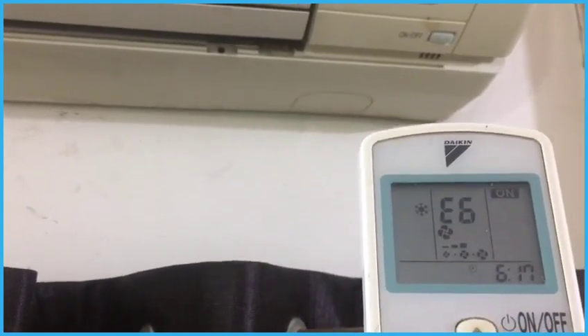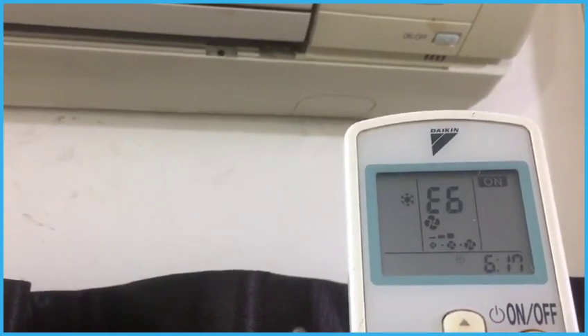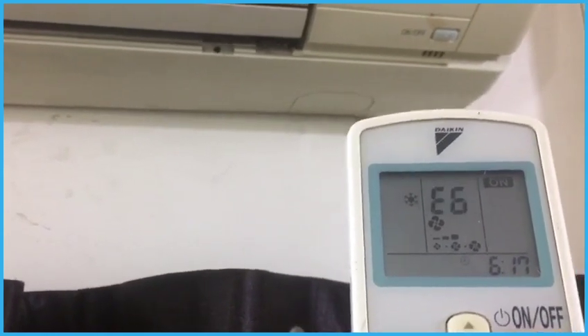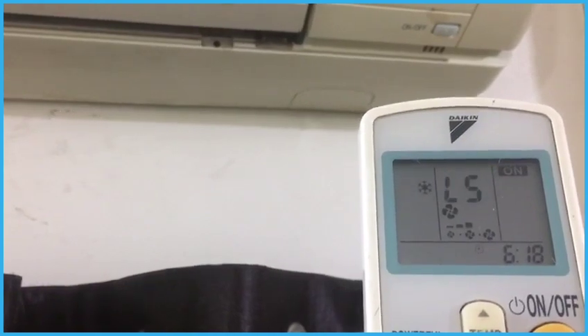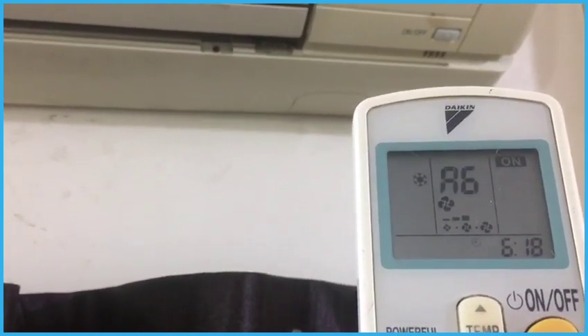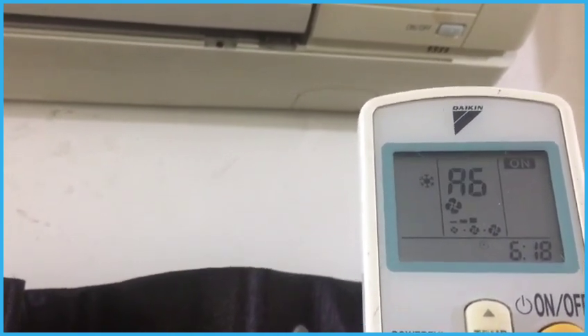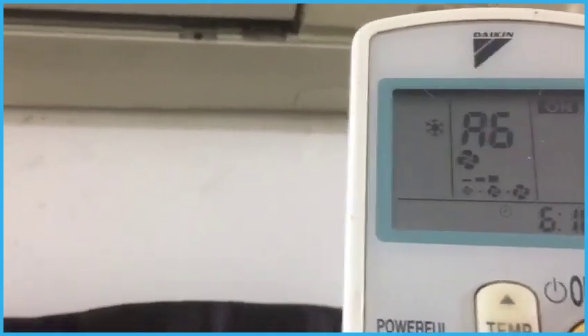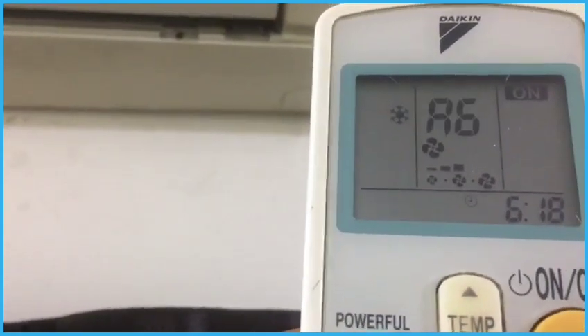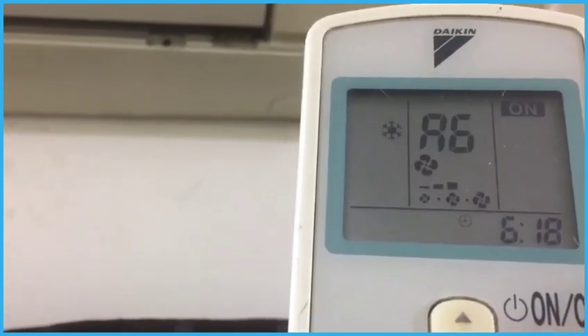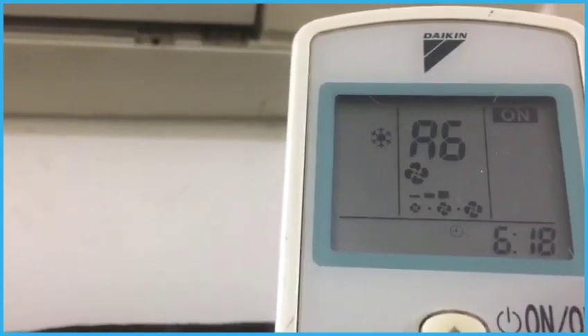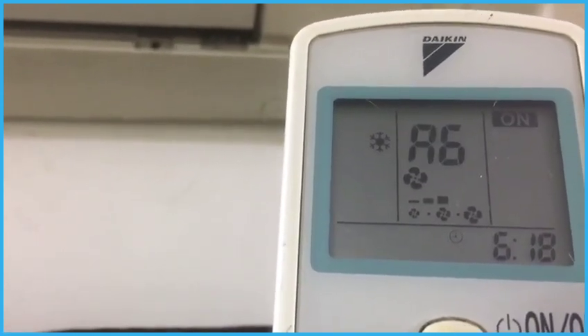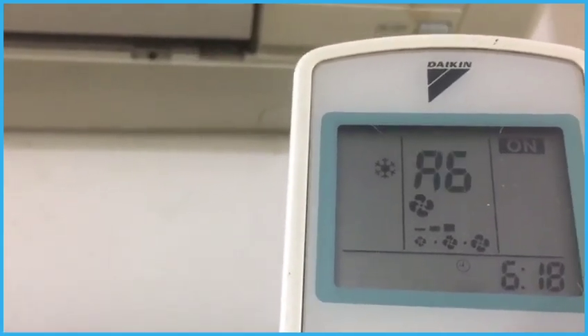Be careful and listen to the beep sound. It is a long beep. It means this machine is not working because A6 error code is there. For more detail, please visit Daikin website India, Daikin India website.